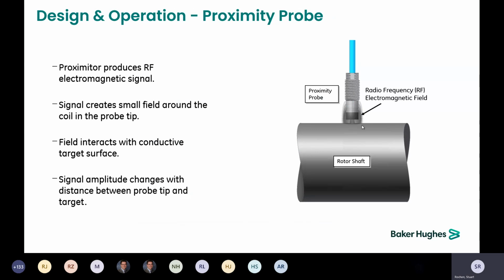Now, how do they work? The Proximitor produces an oscillating signal at a radio frequency, and as that passes through the probe tip, which is basically wound as an antenna, it generates a field around the tip. As a conductive material moves into that field, it generates eddy currents in the surface of the material, and that creates a loading on the signal. By reading that loading and unloading, we are able to measure the displacement.